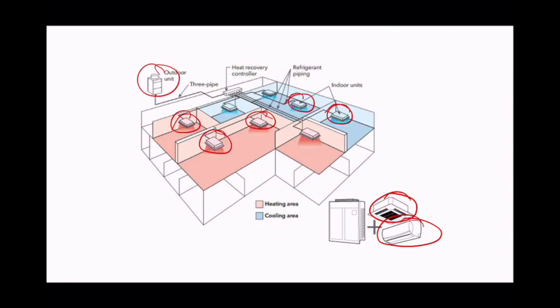If it's a condenser, it'll open up the gas line and the liquid line, and the gas will condense into a liquid and then be brought back. If it's being served as an evaporator for cooling, we'll open up the suction line and the liquid line in that indoor unit. Then we'll have low pressure and run a fan over that refrigerant.